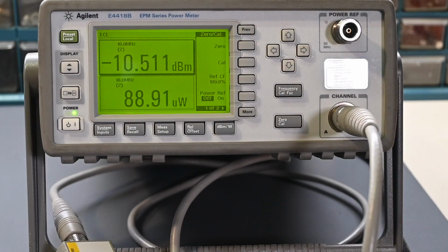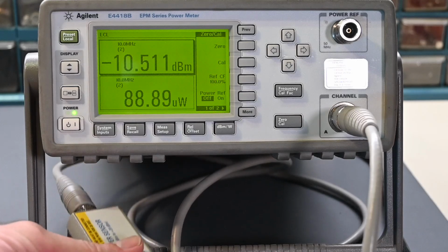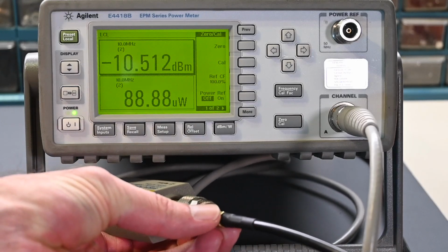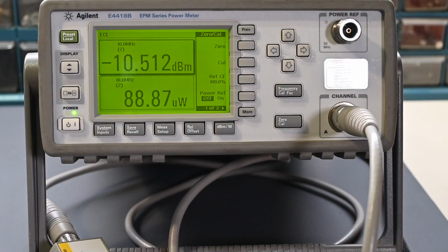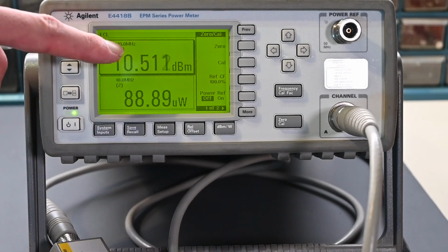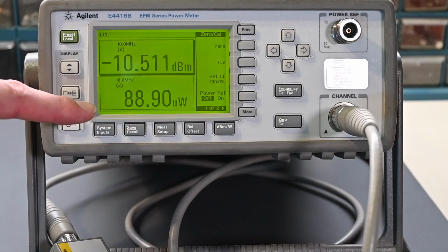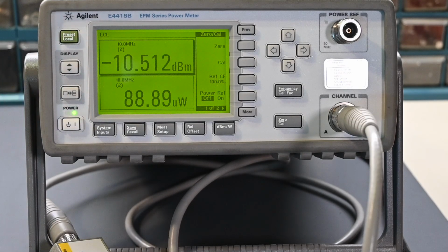So the cable I'm using is actually an RG223, so it's a very low loss type cable, but there is a measurable loss nonetheless. So what I have to do is increase the output of the signal generator just slightly to offset the loss in that cable. Then we know that this point right here, which is going into this power sensor, this will be connected to the spectrum analyzer, and we know that we're getting exactly a minus 10 dBm input to the spectrum analyzer, so that when the displayed value on the screen says minus 10 dBm or whatever level we're at, we know that it's accurate. Because again, we don't want to be a half dB off on our measurements, and you can see that that is occurring right now. This display up here, you can see it's minus 10.5 dBm, and then that's the actual wattage, so 88.9 microwatts.